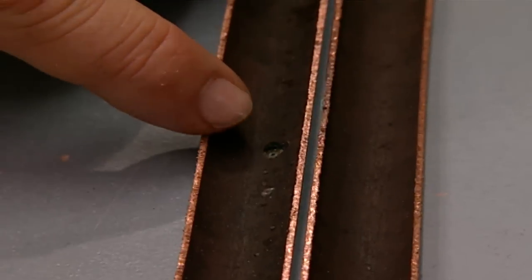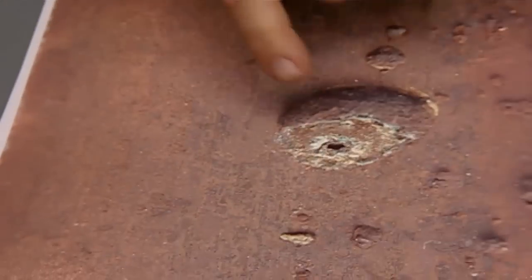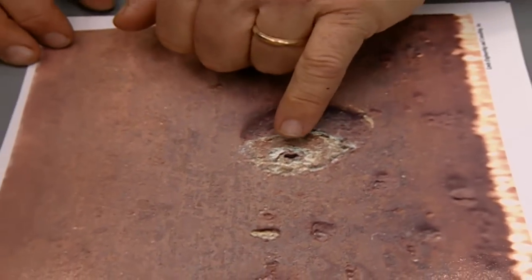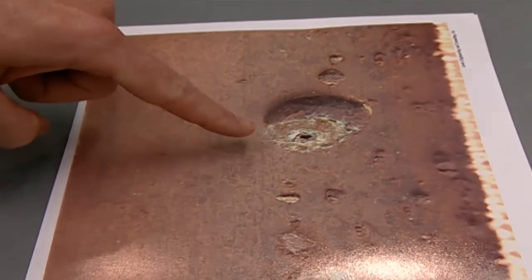When the pipe is split, we see a nodule right here of corrosion, and that was in a variety of places. Under a high-powered microscope, here's the images that we see. You can see one of the nodules. When that nodule is broken apart, you can see there's a pit corrosion point, and there was the presence of iron underneath it. And the corrosion builds up around that little flake of iron.